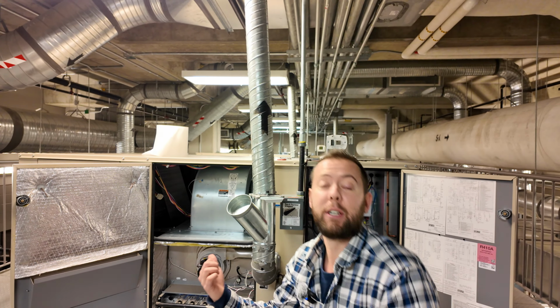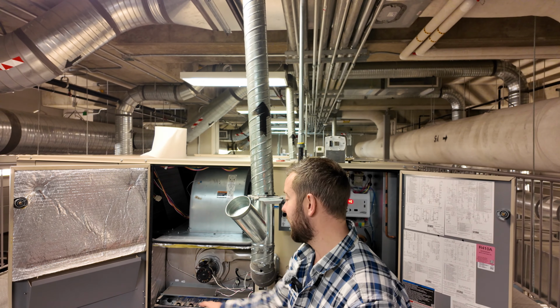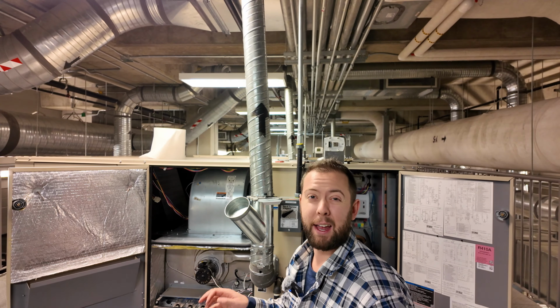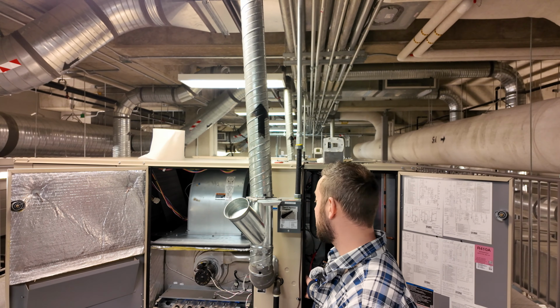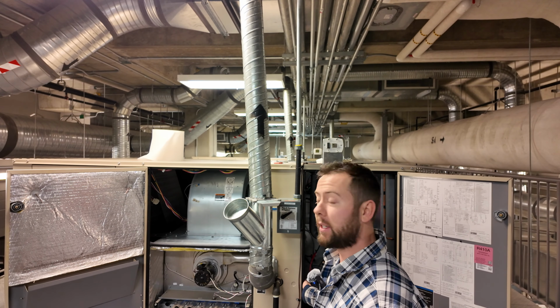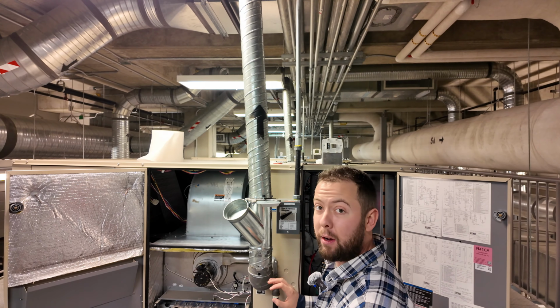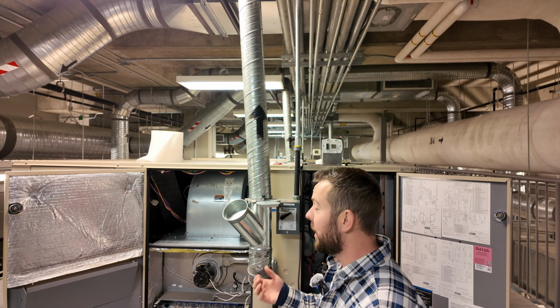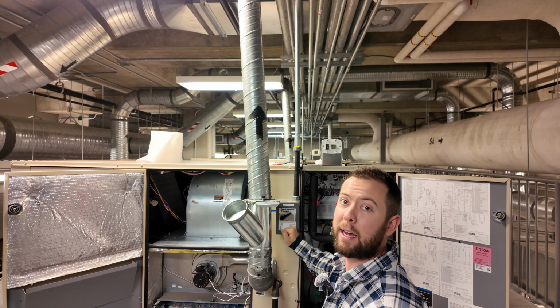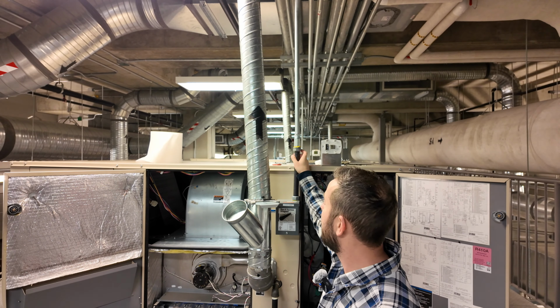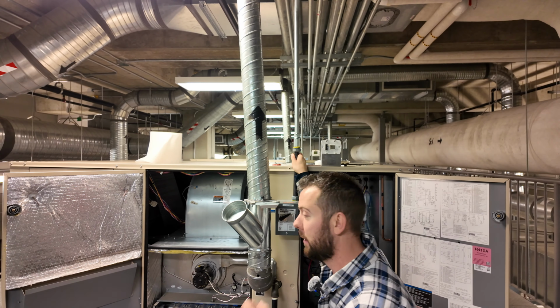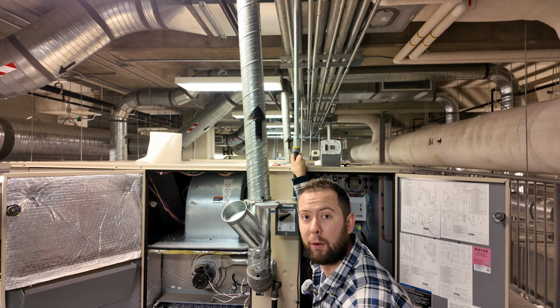That flame sensor, the igniter, they're all easily accessible. The only thing that's kind of a tough spot on this one is the gas valve. But when I have to replace the gas valve, I just take this whole panel out, which can be kind of annoying depending where people mount the disconnect, as this one would be a little bit more frustrating, but very simple design. I really like Lennox unit.